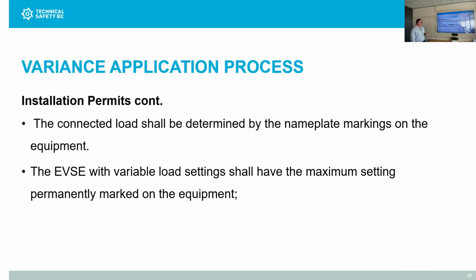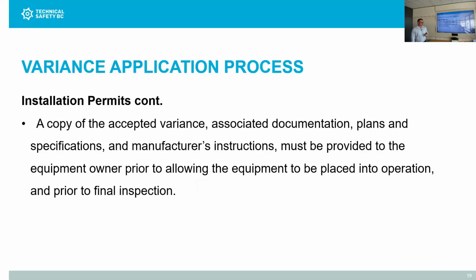Any EVSE system with variable load setting shall have the maximum setting permanently marked on the equipment. I can bring up, I believe a Tesla charger has multiple settings, so for an example like that, you will need to ensure that that maximum setting has been labeled. In addition to that, you'll need a copy of the accepted variance and any associated documentation, plans and specifications, and any manufacturer's instructions must be provided to the equipment owner prior to allowing the equipment to be placed into operation and prior to final inspection.